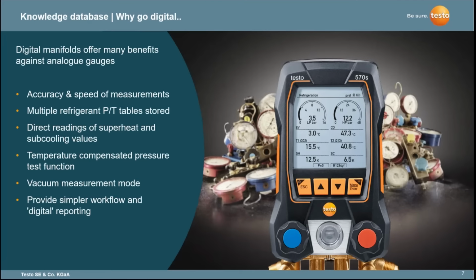Some of the key benefits that digital manifolds generally offer against analog gauges are much higher accuracy and a much faster speed of measurement. Obviously, nowadays, when we're talking about workflow, if your workflow can be sped up, you potentially are not going to be on site so long, and therefore there are cost savings involved. You've also got multiple refrigerants stored in the digital devices. For example, most of the Testo manifolds come as standard with around 100 refrigerants stored in them.